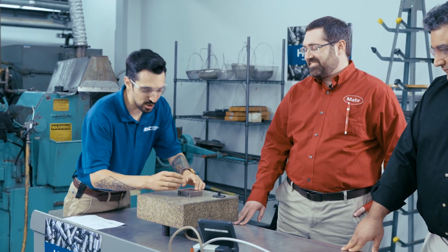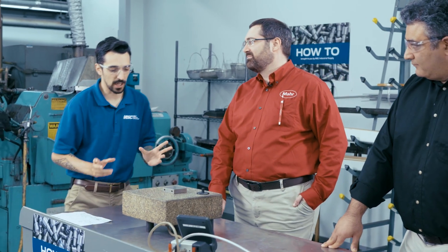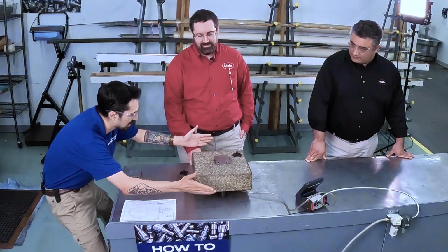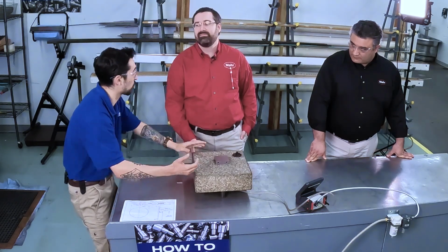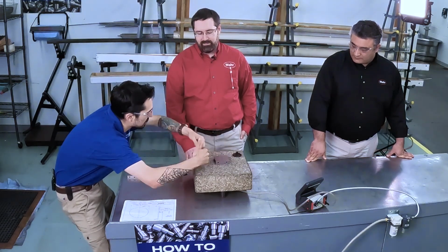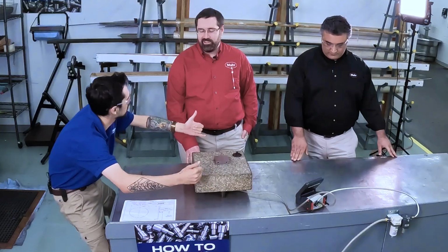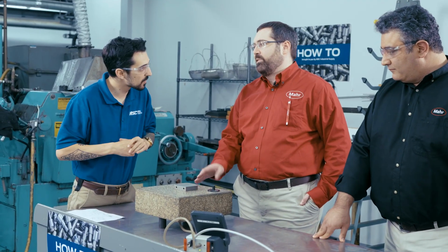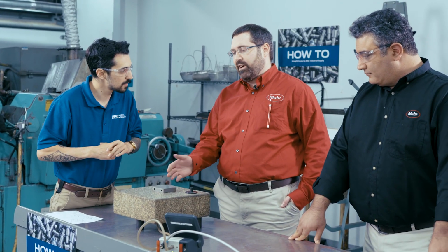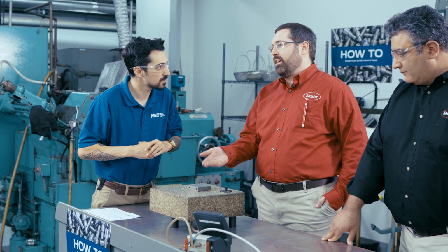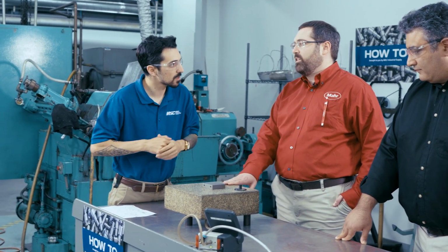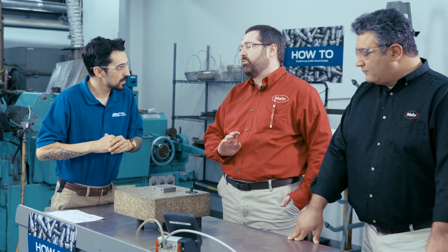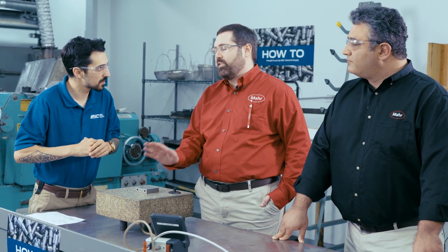So this is awesome. Usually what I would do, and correct me if I'm wrong, if I'm checking flatness in my facility, I still got my big granite, still have my part, but I have to actually use like a dial gauge or a jeweler's gauge to run across. Sure, that's another option. What you get from the benefit of this, though, is that, like those other examples, you have contact. So that means you have to have an actual point contacting the part, whereas this, the probe is recessed below the granite, so it doesn't touch the part at all, so you don't have to worry about scratches or anything else. It's non-contact to the part.